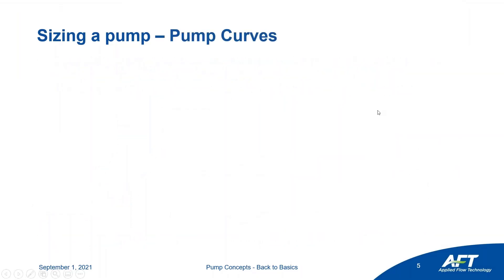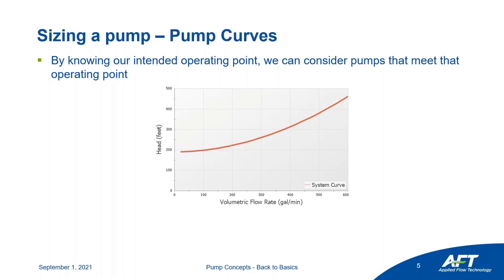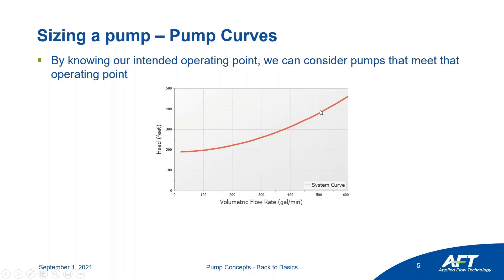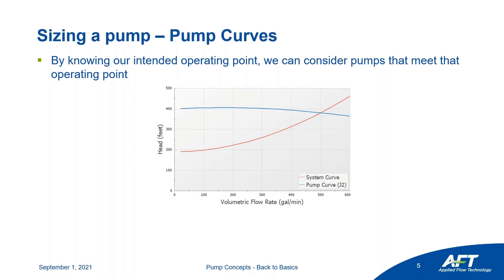Now that we understand the system and our operating point, we can consider different pump options. Looking at our system curve, our operating point was at about 500 gallons per minute and 381 feet of head. As long as our pump curve intersects that point, that will be our operating point depending on the pump. We have an intended operating point of 500 gallons per minute, and the actual realized operating point will be where the pump curve intersects the system curve. Because we're sizing, we're selecting based on our intended operating point — as long as a pump curve intersects the system curve at 500 GPM, that pump will meet our flow rate requirement.